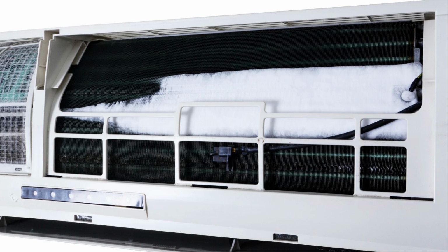What causes HVAC coils to freeze? 1. What causes HVAC coils to freeze? There are a number of things that can cause HVAC coils to freeze, including low refrigerant levels. When there is not enough refrigerant in the system, the coils cannot absorb enough heat from the air, which can cause them to freeze. Restricted airflow. If the airflow over the coils is restricted, they cannot transfer heat efficiently and may freeze.